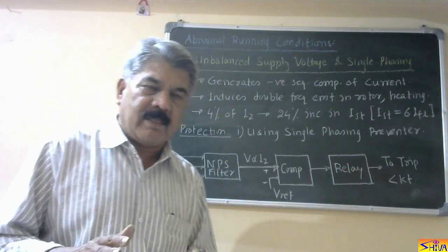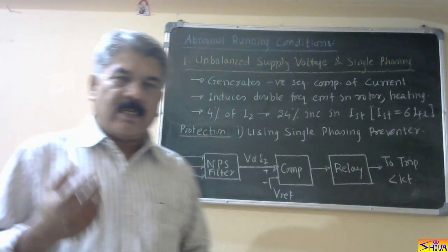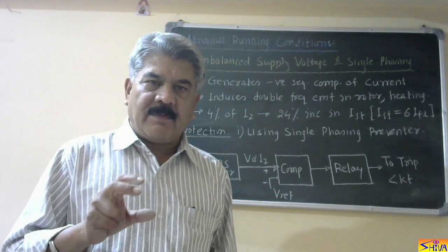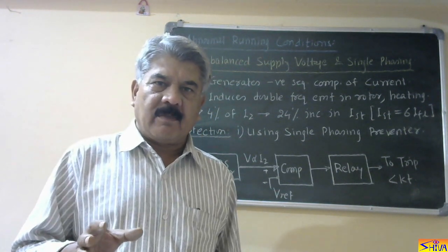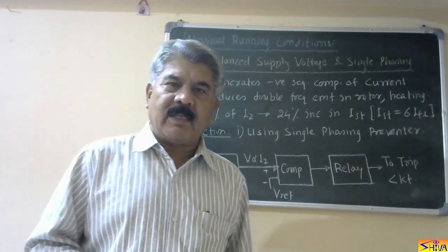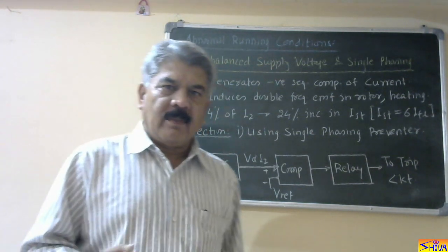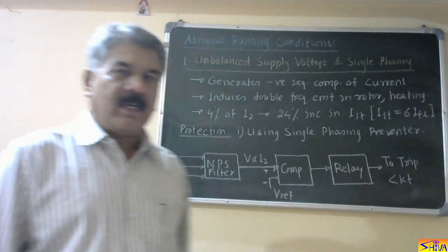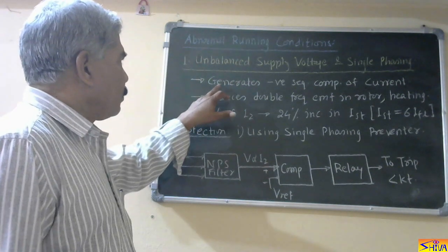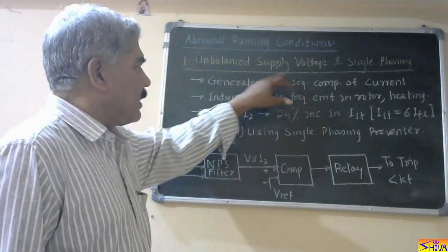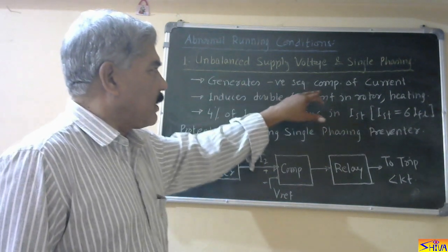Unbalanced supply voltage means the motor is connected to a three-phase supply, and this three-phase supply voltage is not balanced. So when the three-phase supply voltage is not balanced, we know that a negative sequence component of the current is generated.